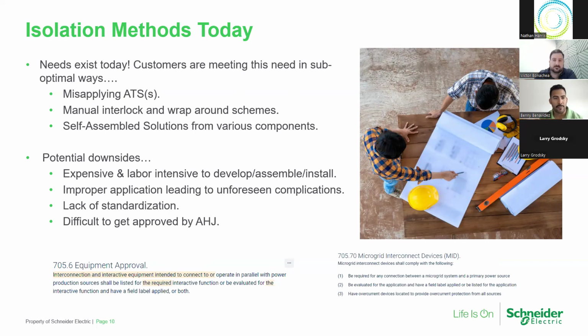You want to make sure you get those installation requirements hashed out before the rest of the job site. Improper application: again, if you're using an automatic transfer switch for isolation, the UL 1008 listing is specifically to transfer load to another power source, not for isolating. That's not what the UL listing was approved for. So you could see some unforeseen complications if you decide to go that route.